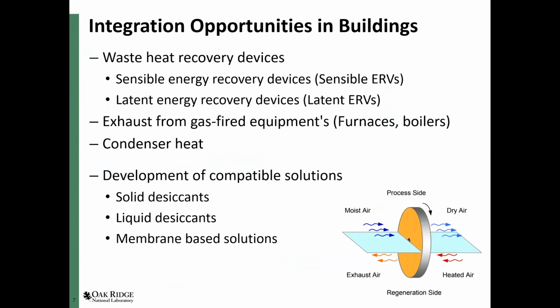Elaborating a little bit more on some of the component level details, essentially waste heat recovery systems have been considered, and there has been a lot of effort on the so-called ERVs, energy recovery ventilators. Most of them are sensible devices, right? And if I ask you how many studies have been done on latent energy recovery systems, essentially there are not many. There have been some developments looking at how you can recover the moisture from outgoing air and use that latent heat for the incoming air. But again, that is an area which requires further development.